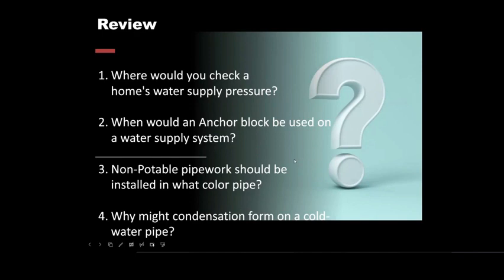So to prevent that, you can insulate it, you can lag it, which means there's an air barrier that doesn't move anywhere. So the air close to it gets cold, the air on the outside of the lagging is warm, and they're never in direct contact. So that can prevent condensation.